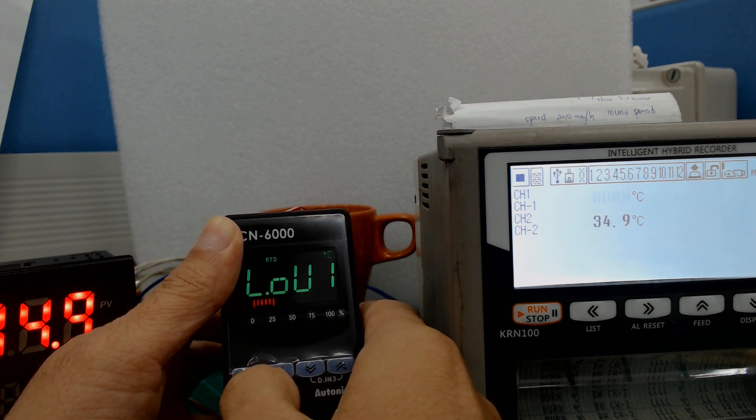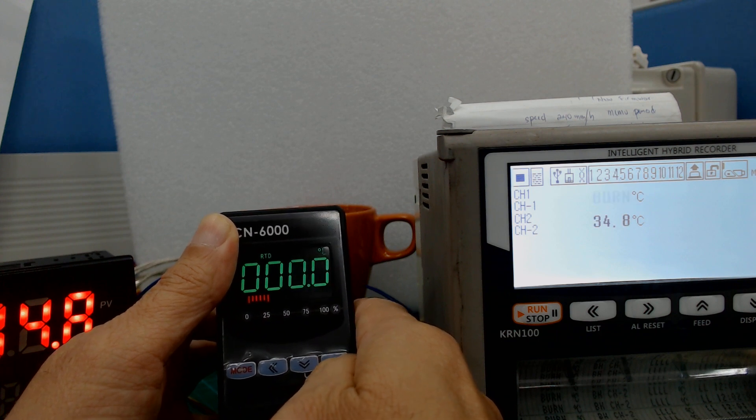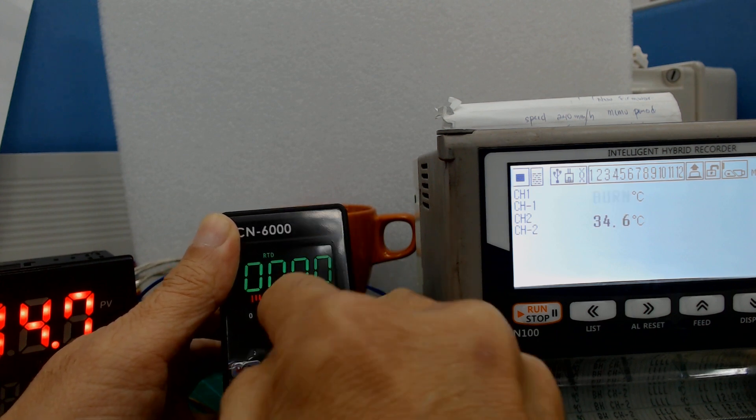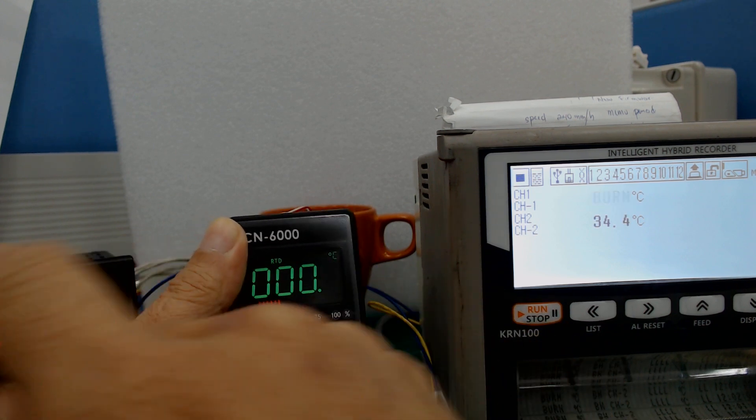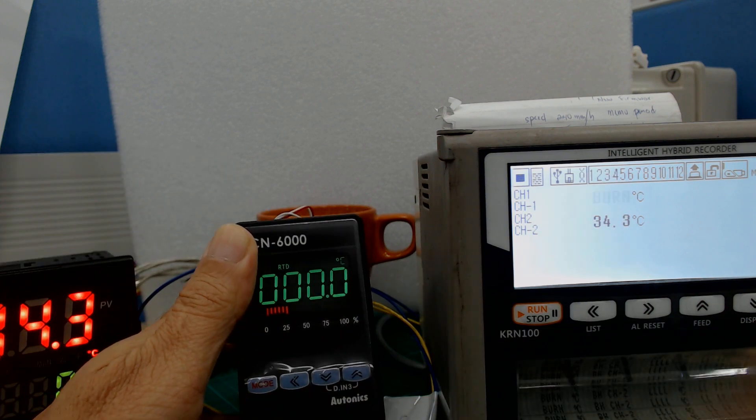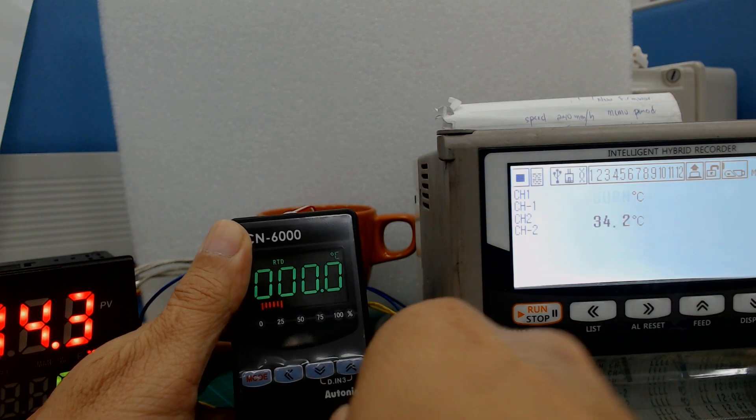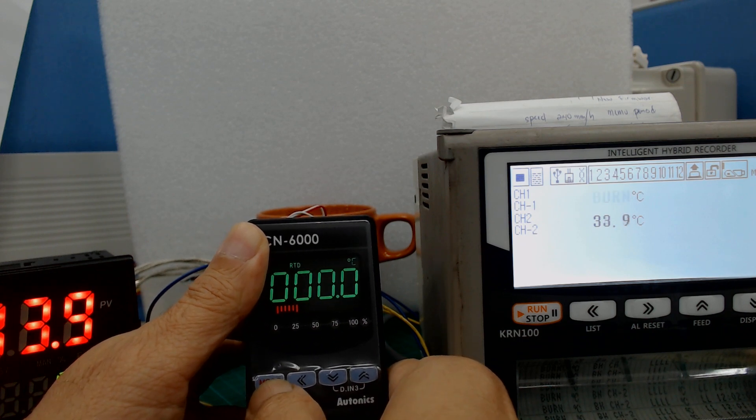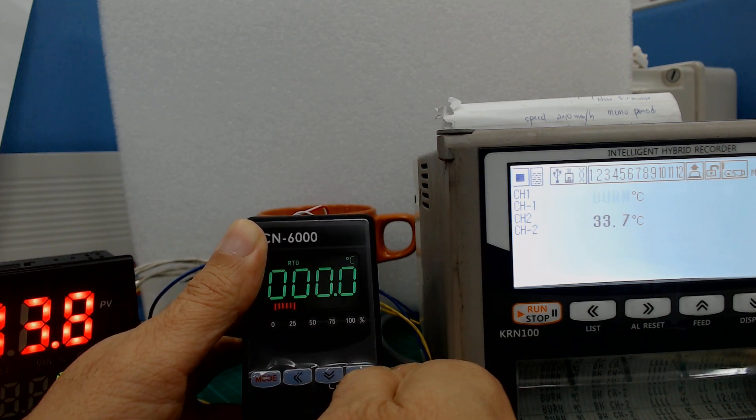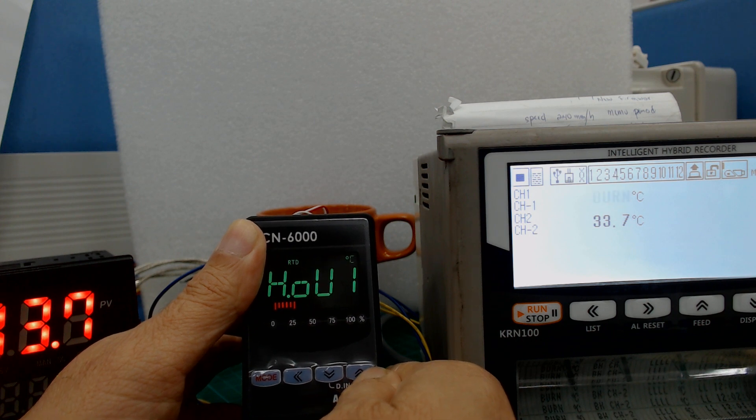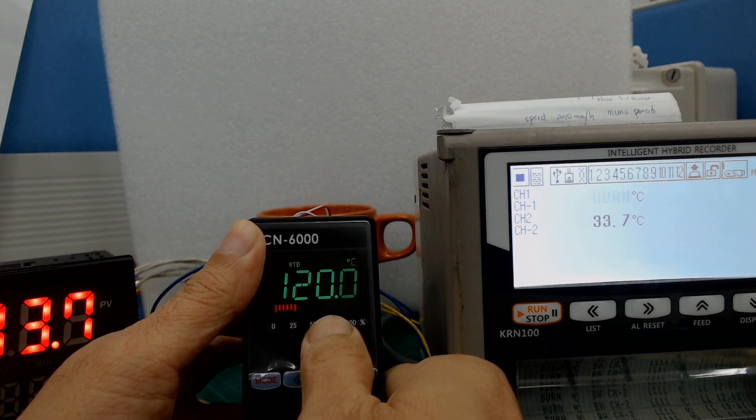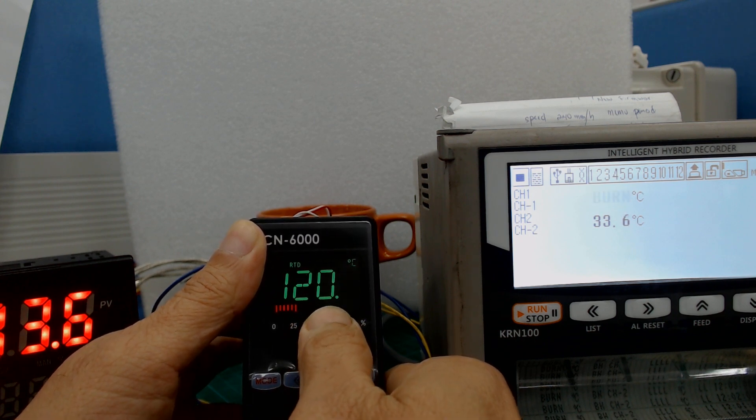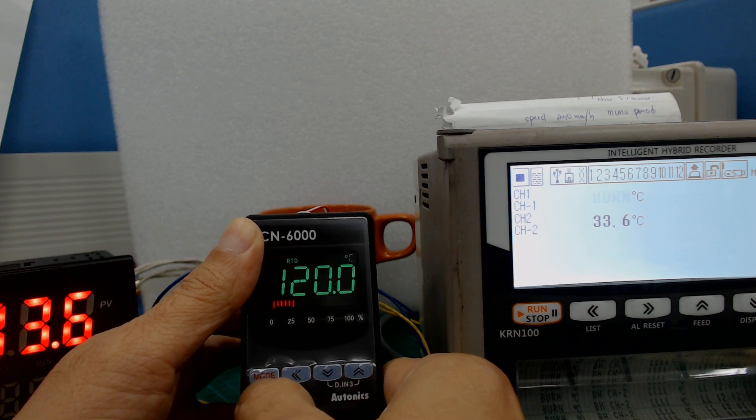So low one is zero, this is the scaling for the output number one for the CN series. Zero, and then low one zero Celsius, and then high one output. So I set the scaling 120 Celsius.